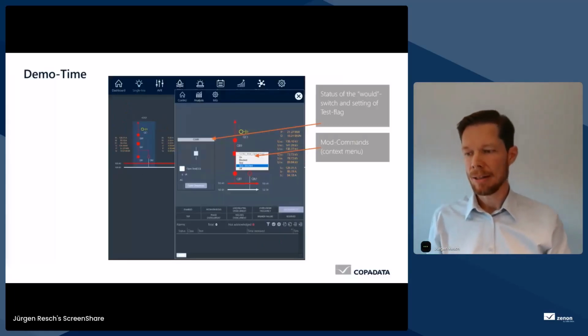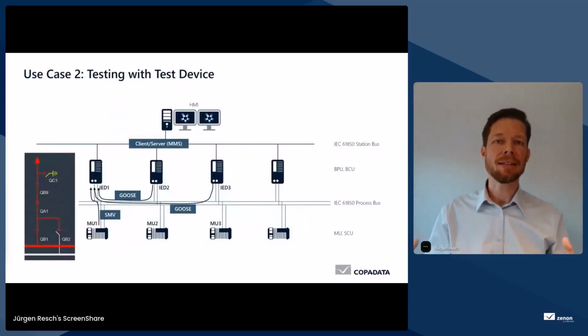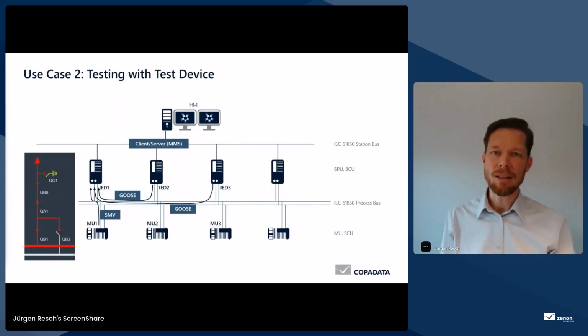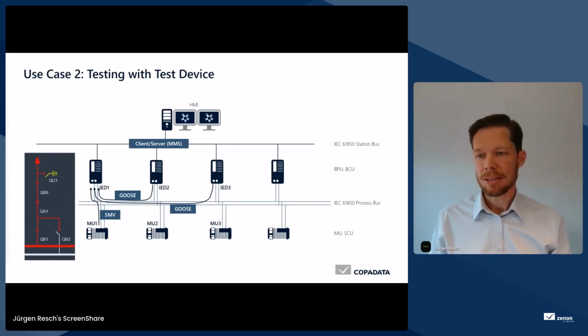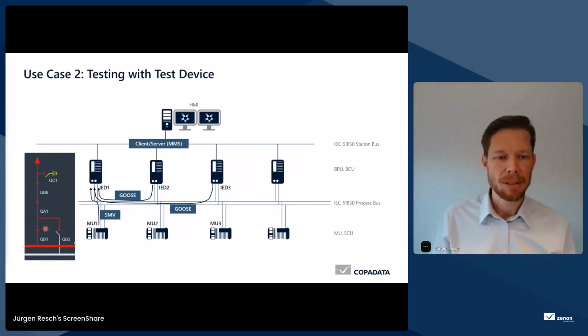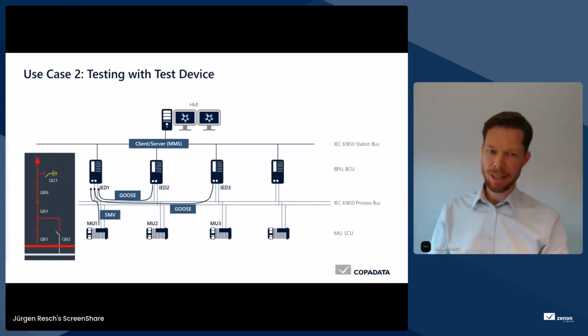Now we go back to PowerPoint and talk a little bit about how it is when we are entering a test device that is injecting GOOSE messages for testing devices. And for that, we look into this construction again. So we have one IED, IED1, that is subscribed to two IEDs for GOOSE messages, and to one merging unit for sampled values.